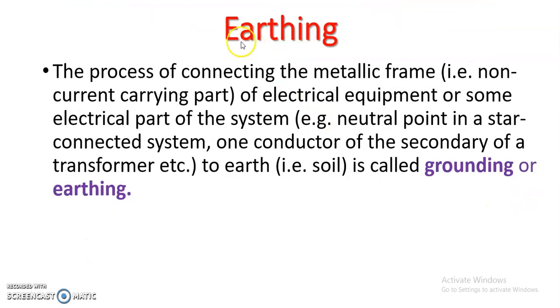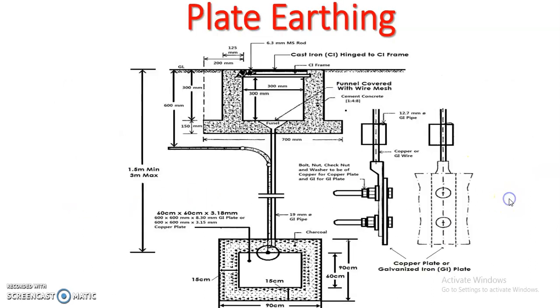Then what is earthing? So the process of connecting the metallic frame, that is non-current carrying part of an electrical equipment or some electrical part of the system, that is neutral point of the star connected system or one conductor of the secondary of a transformer or neutral point of the generator to the earth or soil. It is called as grounding or earthing. Then next, the type of earthing which can be used for a plinth mounted substation. It can be pipe earthing or plate earthing. We can also use the pipe earthing in case of plinth mounted substation, or we can use plate earthing in case of this plinth mounted substation.